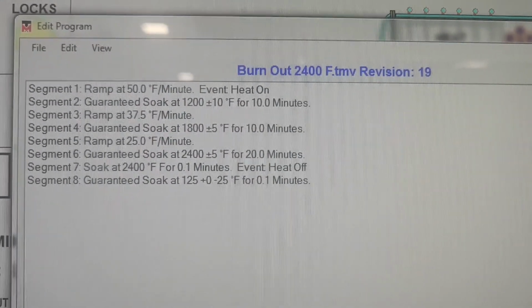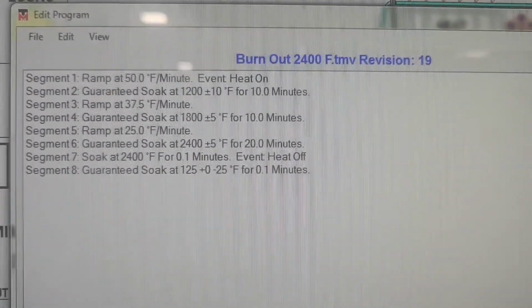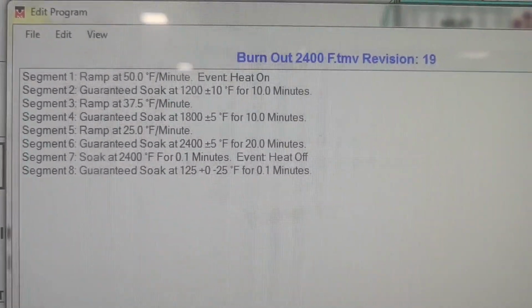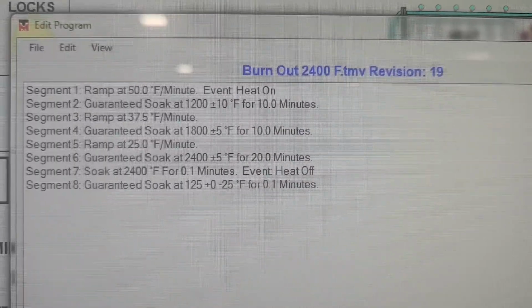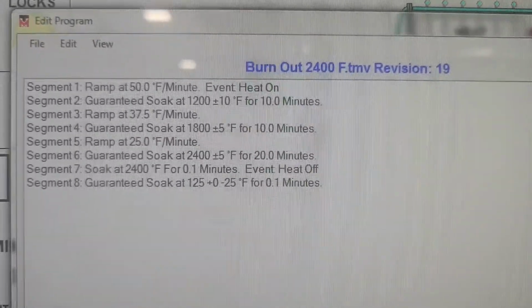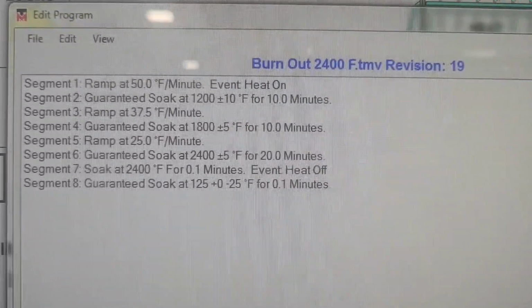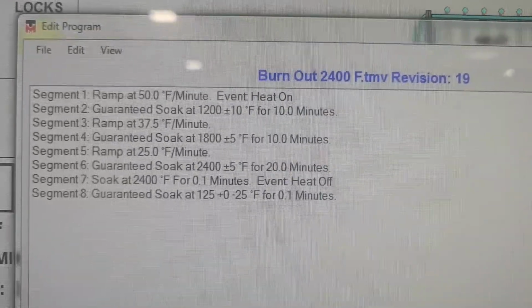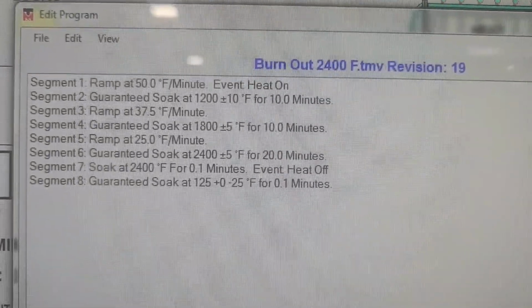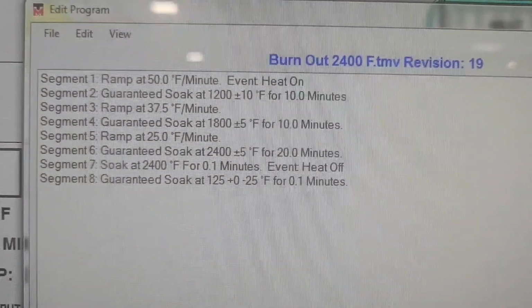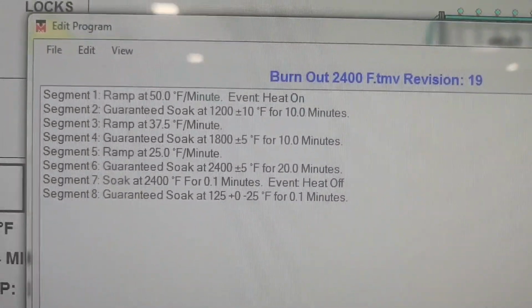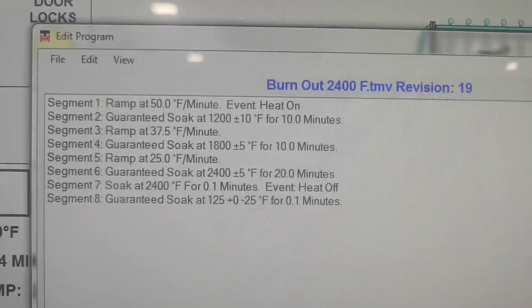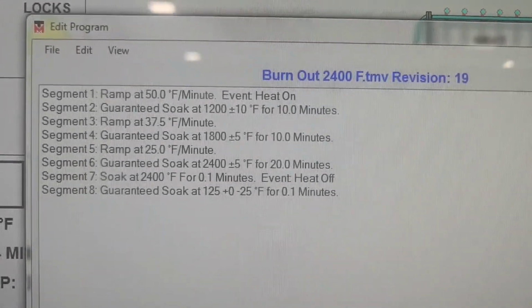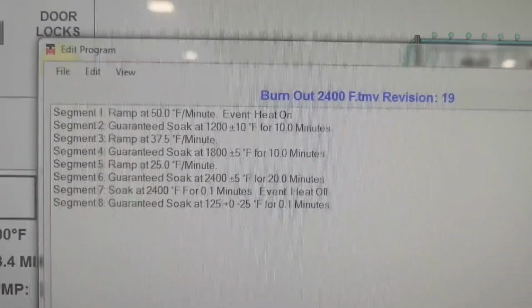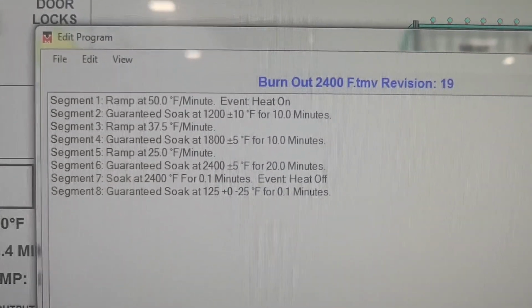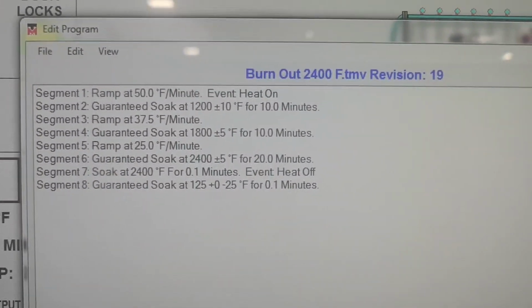You can see that I pulled up the program. The program's very simple, line by line. It's ramping up and holding a temperature at a certain point for a period of time and then ramping to the next temperature. The computer does assist you to write these programs, but they're very simple, deciding on what ramp speeds, what amount of time you're going to be holding at different temperatures, and then when you're shutting the heat on and off and putting it into cooling cycle.